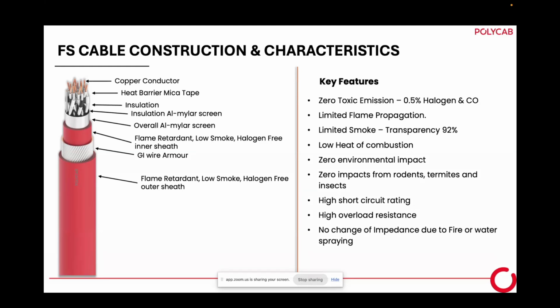Zero impact from rodents and termites. We have a material in this compound, in this jacket, so rodents or termites do not come. High short circuit rating: here the short circuit rating temperature is high. High overload resistance: overload resistance is also high. It does not melt immediately. Here one thing I should say is that the insulation materials are cross-linked. Many people know cross-linking, and for many people maybe it is a new term. So briefly, I will tell you what that is.